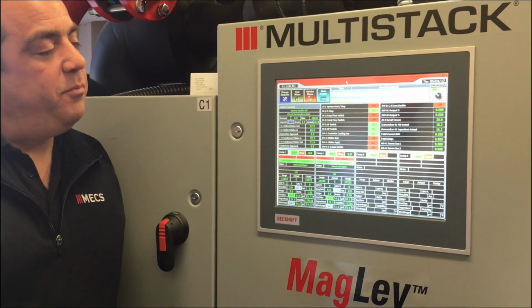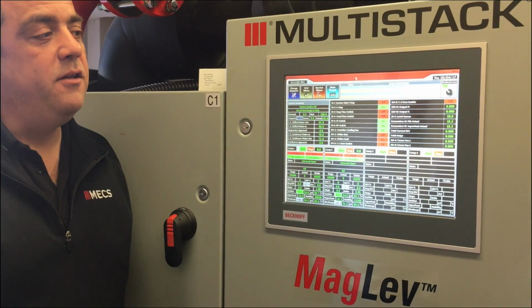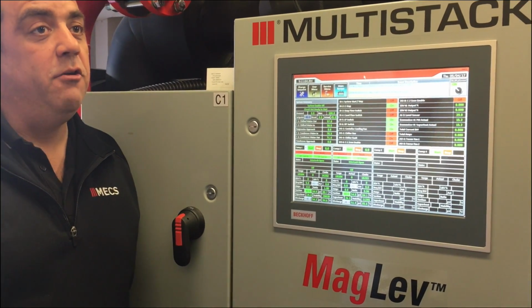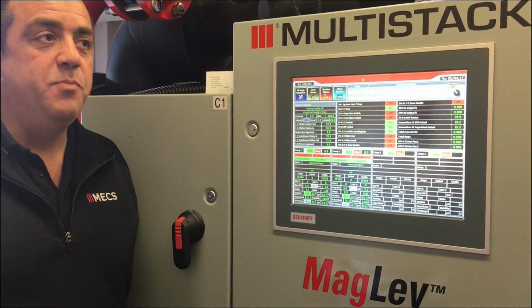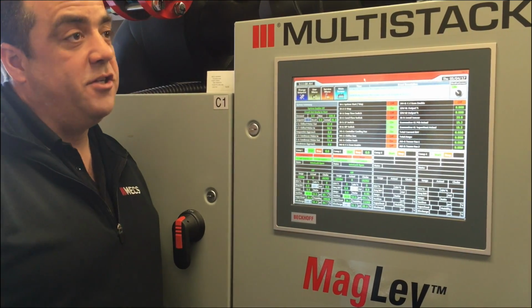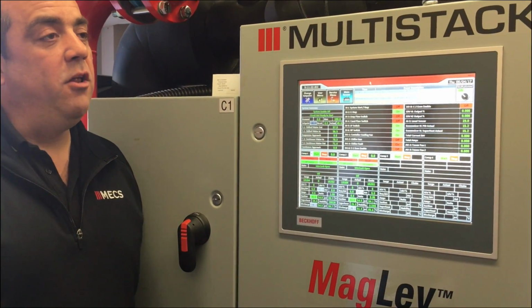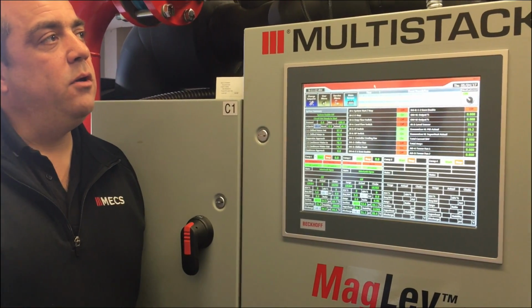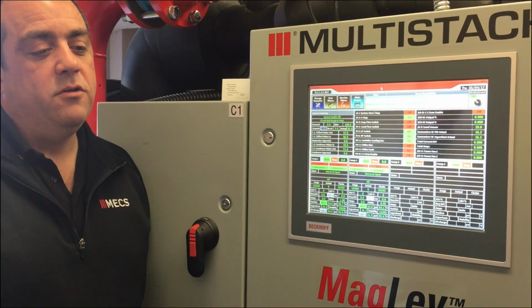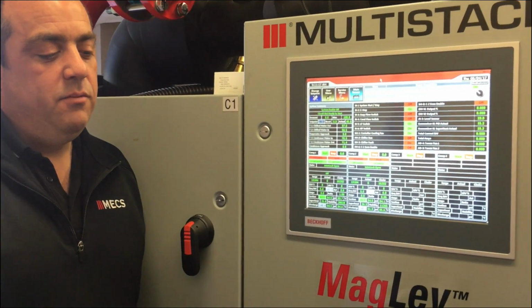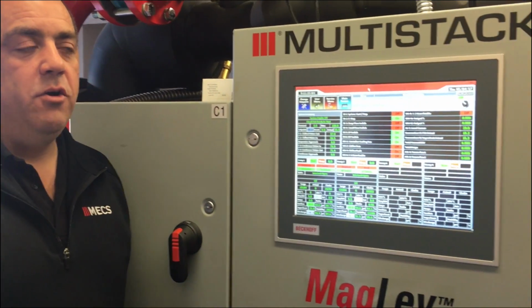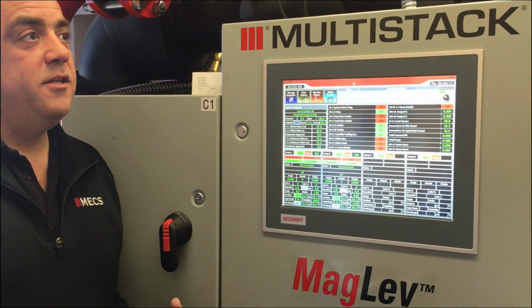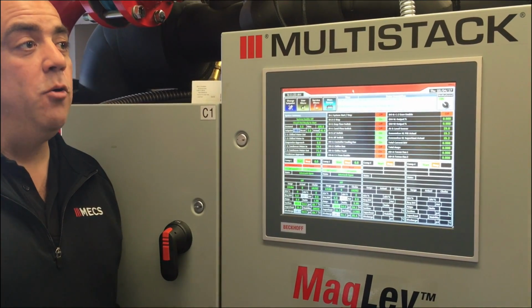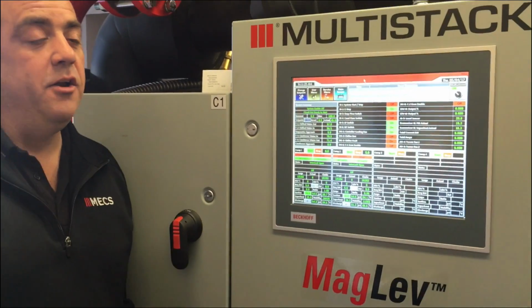So the real big thing is the efficiency. The spinning mass is so much lighter. It takes a whole lot less energy to get it up to speed. It takes a whole lot less energy to stop it. No metal on metal parts. No loss of efficiency through oil. So not having oil, we don't have to worry about oil heaters, or piping restrictions. Cycling's not an issue, because we're not worried about trapping oil in certain parts of the machine and then having it log and not work.